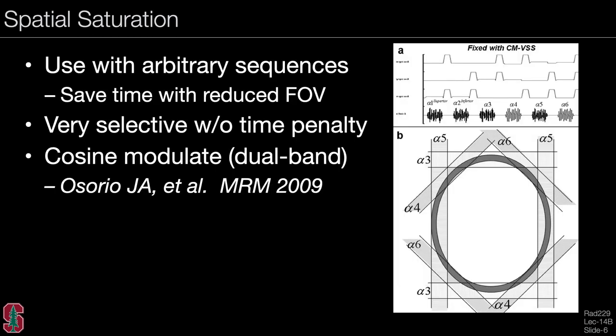Spatial saturations can be used with arbitrary sequences. As shown in the diagram, you can have saturation bands in different directions, building up a non-square or nearly elliptical saturation region. When doing a saturation pulse, you don't actually care about the phase of the excitation, so there are various tricks available: you can make very selective pulses, or cosine-modulate them to excite two saturation bands at a time. There is a lot of interesting work with saturations explored in RF pulse design courses.